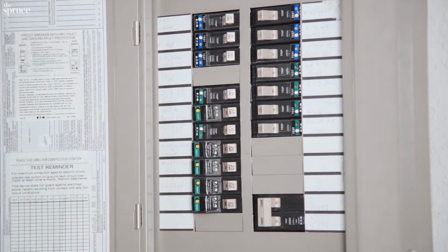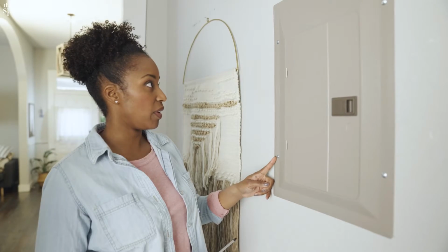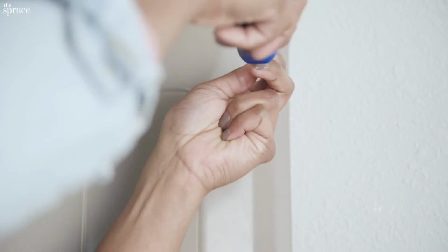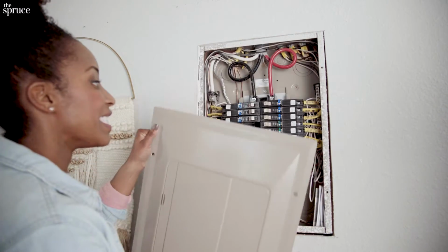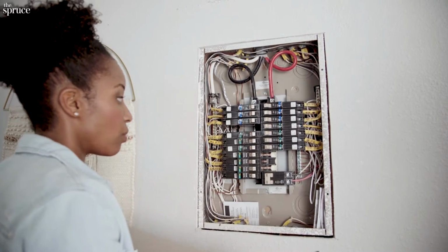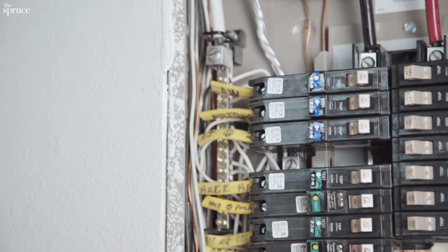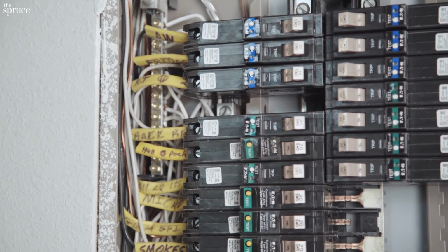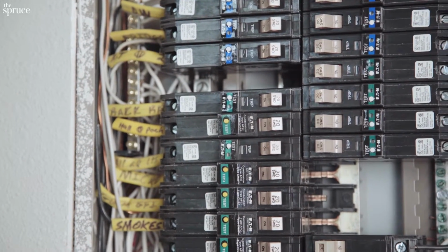Now I'm going to remove the dead front cover by removing these screws. And I like to remove the bottom screws first so it doesn't fall down on me. And I'm making sure not to touch anything inside of the panel while I'm removing this cover. This is my sub-panel, and I shut off the power lines to these wires at the main panel.